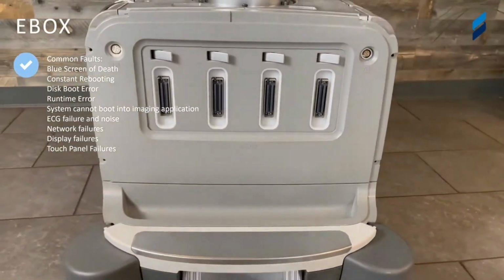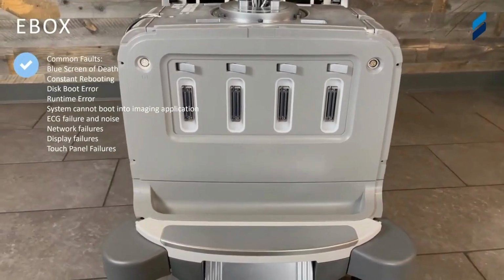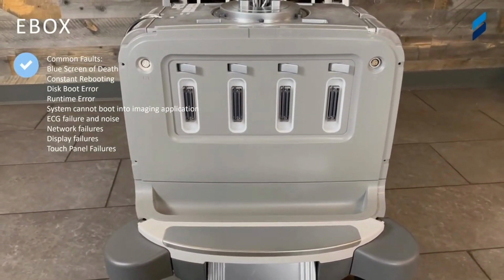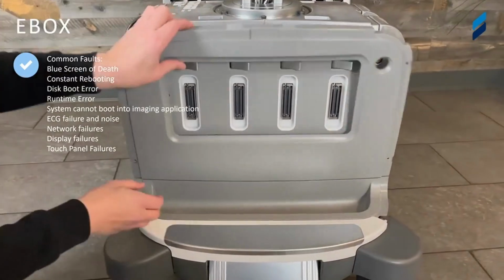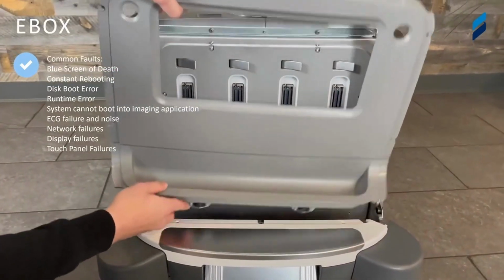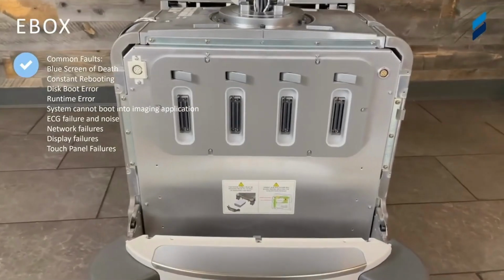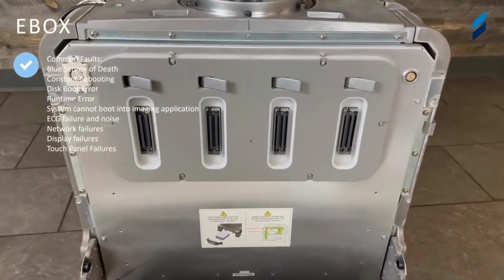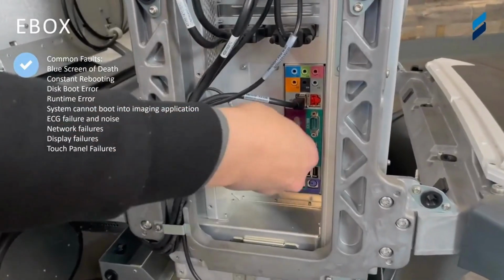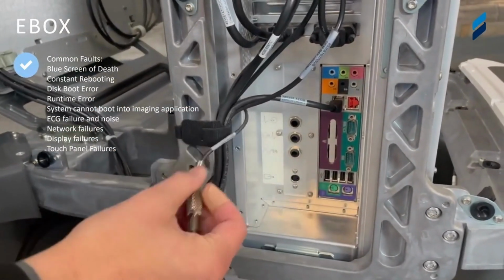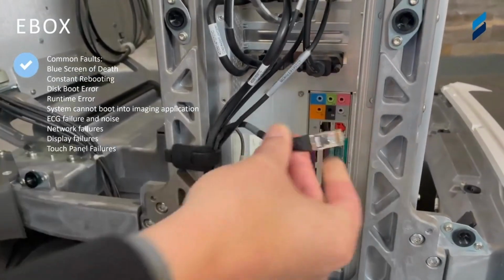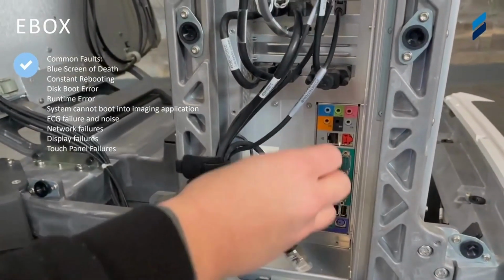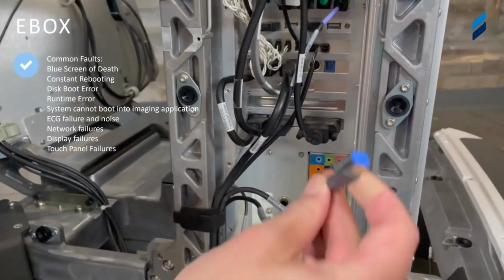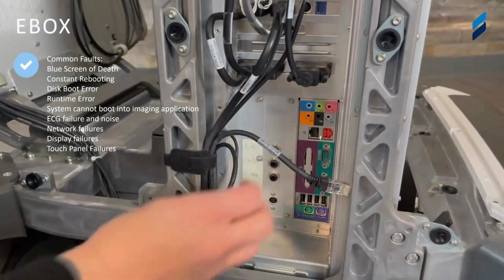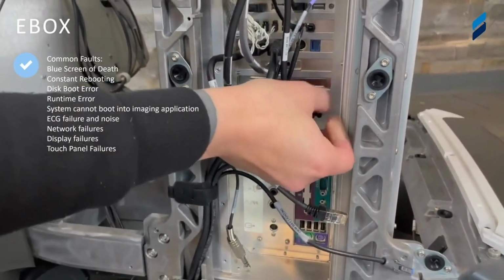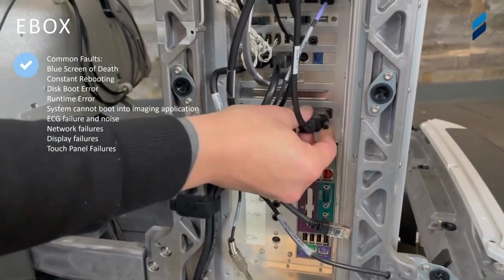So common faults of the Ebox are going to be your blue screen of death, constant rebooting, disk boot errors, a lot of runtime errors. System can't boot into imaging, so kind of a premature fault before it gets to the imaging screen. ECG goes through it, so EKG failure or noise. Network failures, obviously display failures, touch panel failures, kind of all over the board because that's a central processing unit for everything. So now we're going to go disconnect all the connectors.